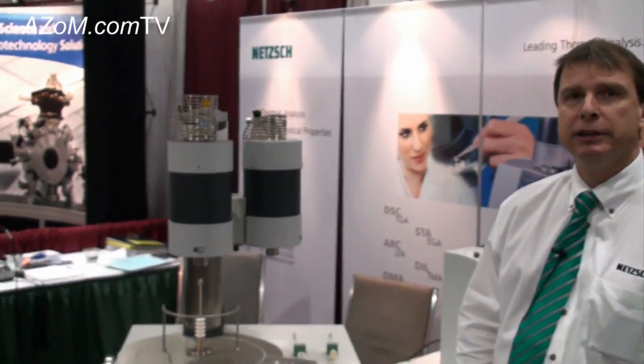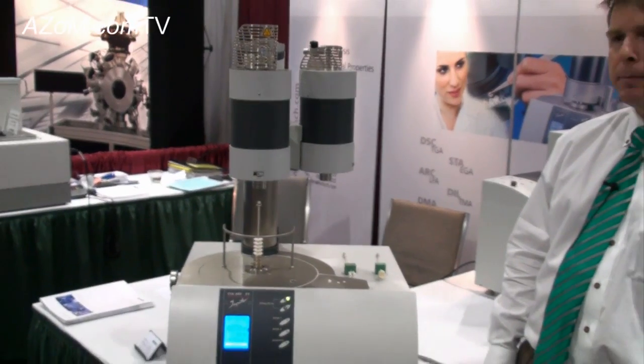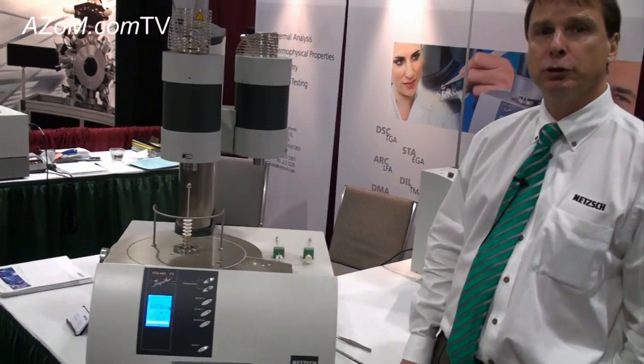This is Cameron Chai from Azom, and today I'm speaking to Dave Sheppard from NETZSCH Instruments. He's going to be telling us about their STA449F1, which is a simultaneous thermogravimetric analyzer and differential scanning calorimeter. So we are measuring both the mass change of a material and also whether it gives off or absorbs energy.